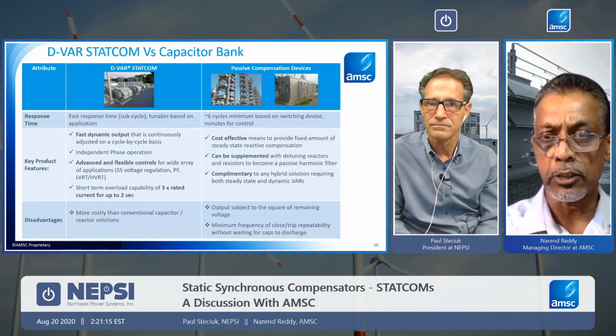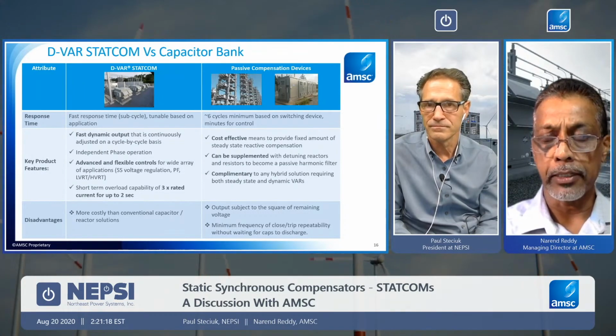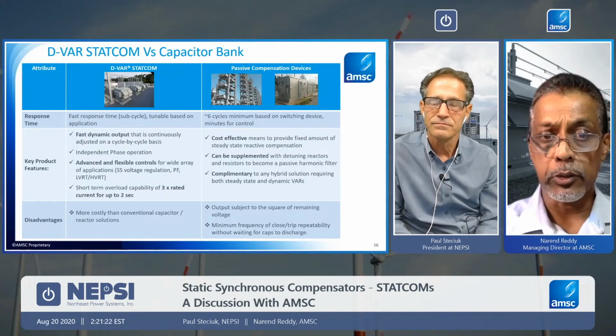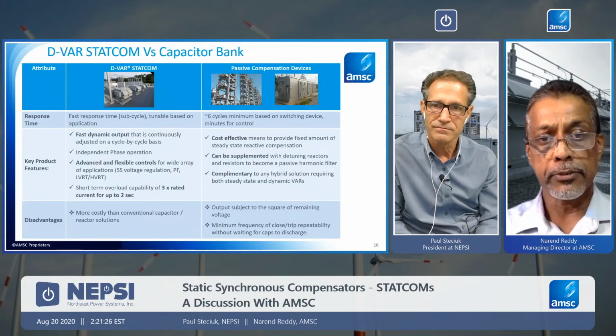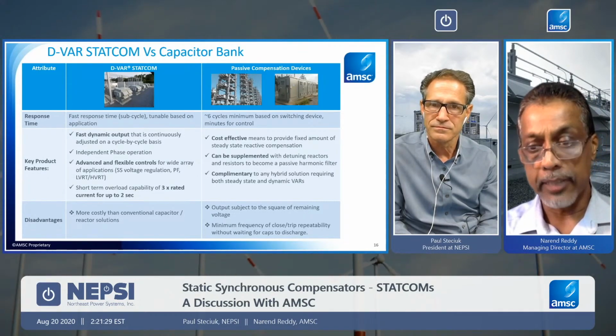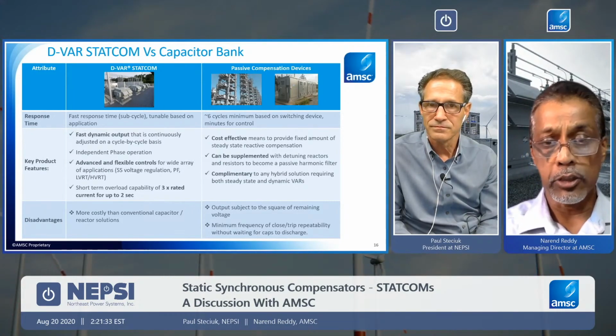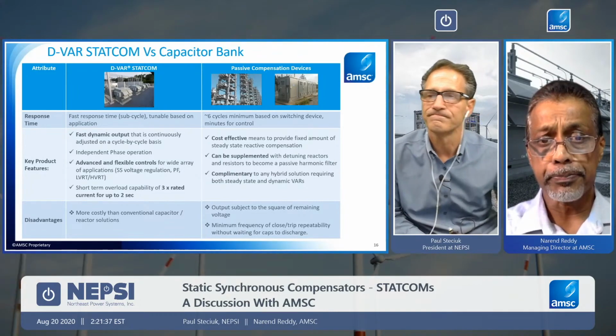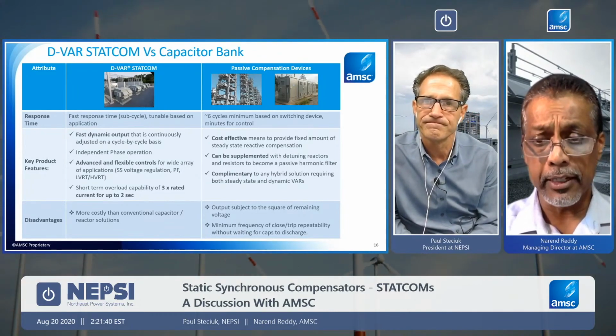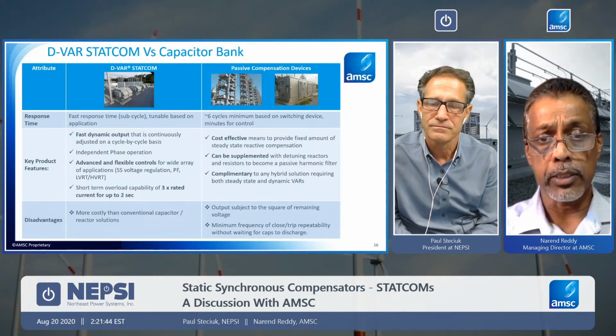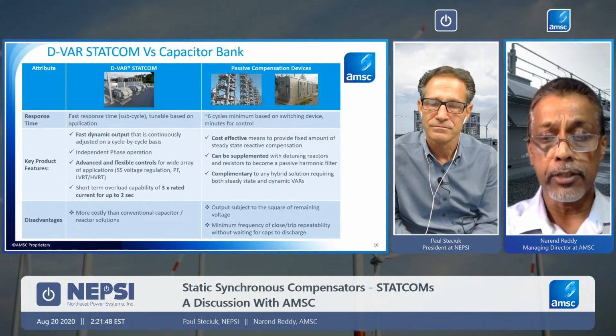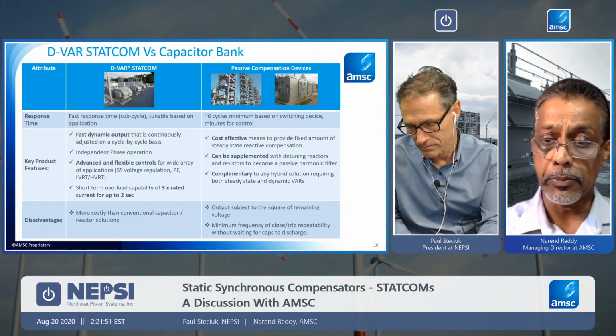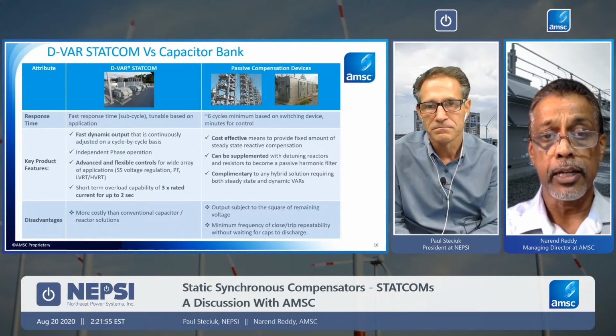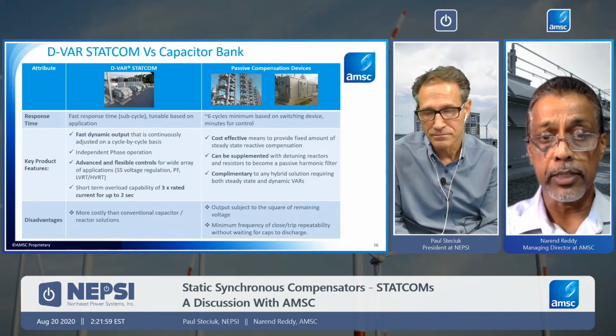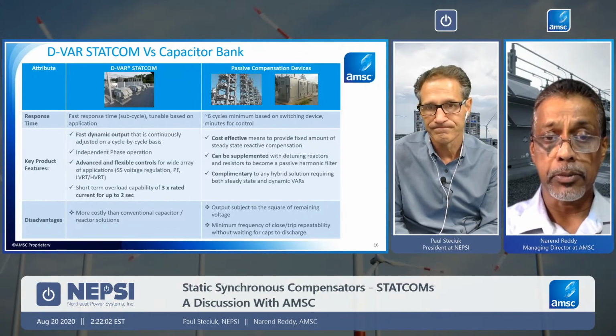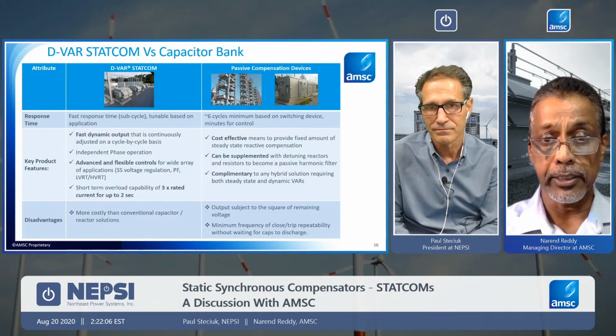You really don't want to be switching these devices too fast either, because it's going to do a lot of harm or put a stress on the switching devices. As I mentioned on the product features, it's fast dynamic output that's continuously adjusted on a cycle by cycle or a millisecond basis. There is no step functional output on the STATCOM. Another key one is that the STATCOM is really an independent phase operation device. In other words, if you're looking for a transient response, a transient might be a fault which may not be balanced. It could be a highly unbalanced fault. The STATCOM, if its job is to respond to that SAG event, fault response, then it would respond on an independent phase basis, depending on what it is reading.